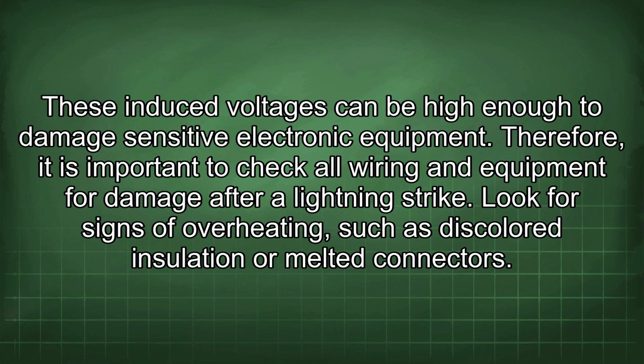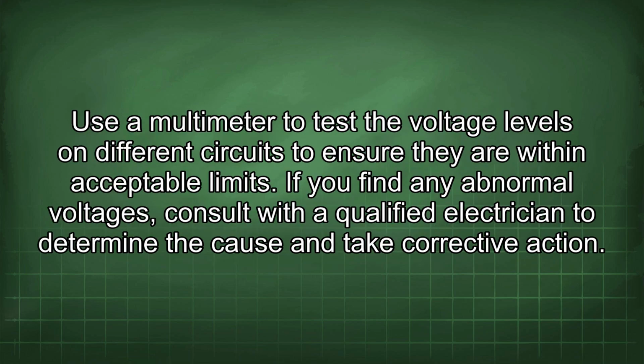Look for signs of overheating, such as discolored insulation or melted connectors. Use a multimeter to test the voltage levels on different circuits to ensure they are within acceptable limits. If you find any abnormal voltages, consult with a qualified electrician to determine the cause and take corrective action.